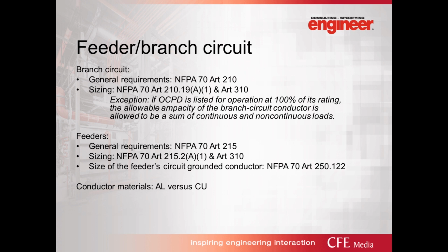The size of the feeder circuit grounded conductor is based on Table 250.122 in NFPA 70. For sizing conductors in a low voltage system, we use Table 310.15(B)(16).